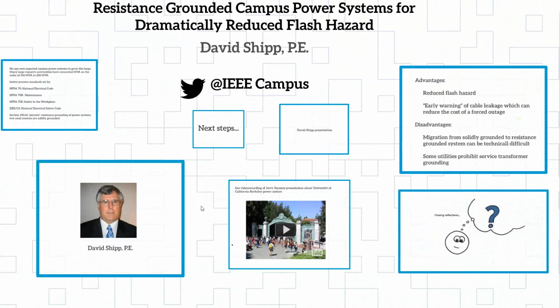But here's the thing: if I'm solidly grounded and I've got 20,000 amps of fault current available there, and say I'm bumping a 15,000 amp magnitude into this confined box, you're going to ionize all the material in it. It's going to quickly escalate into a three-phase fireball and melt everything down. And then the damage, now if it's contained in the metal box per the standards, someone's not going to get hurt as a rule unless he's got the door open. But the damage is going to be massive. You're going to be replacing it.